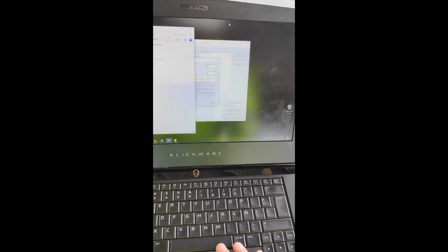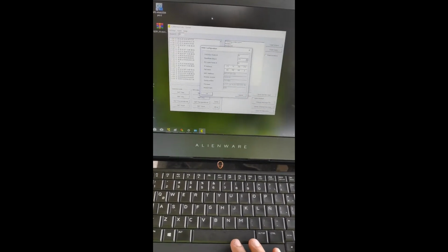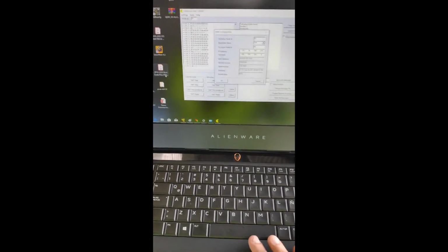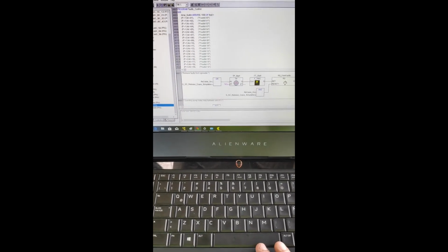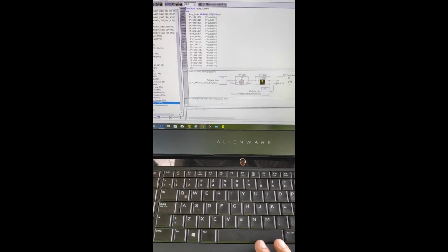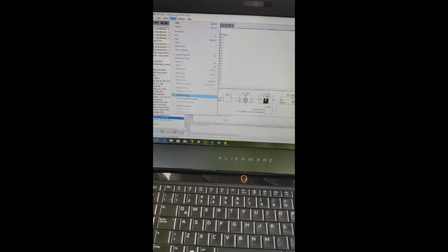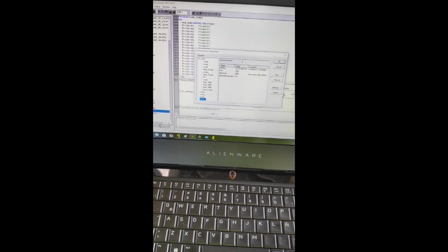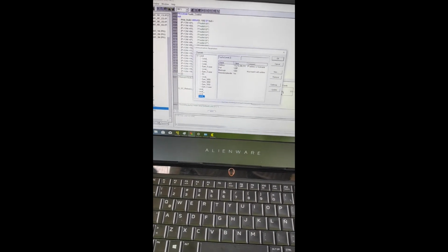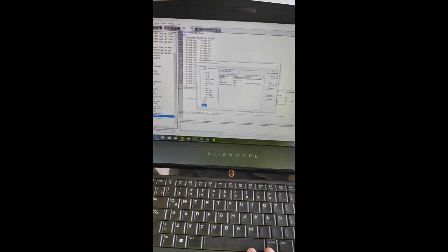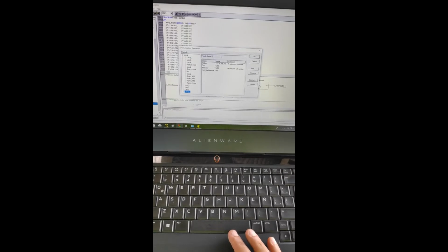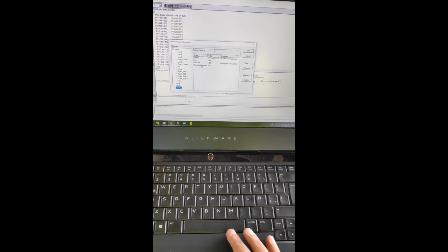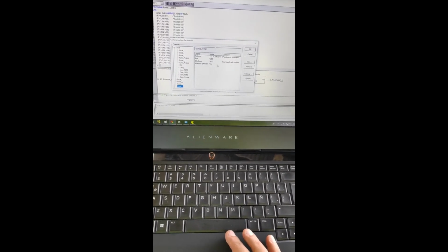After adjusting the IP address, we go to the Codesys program, open the Codesys. Program file, and then from online we go to communication parameters, make new communication, and then change the IP to the same IP of the CPU, and the block size should be 1400, and the Motorola byte order has to be yes.